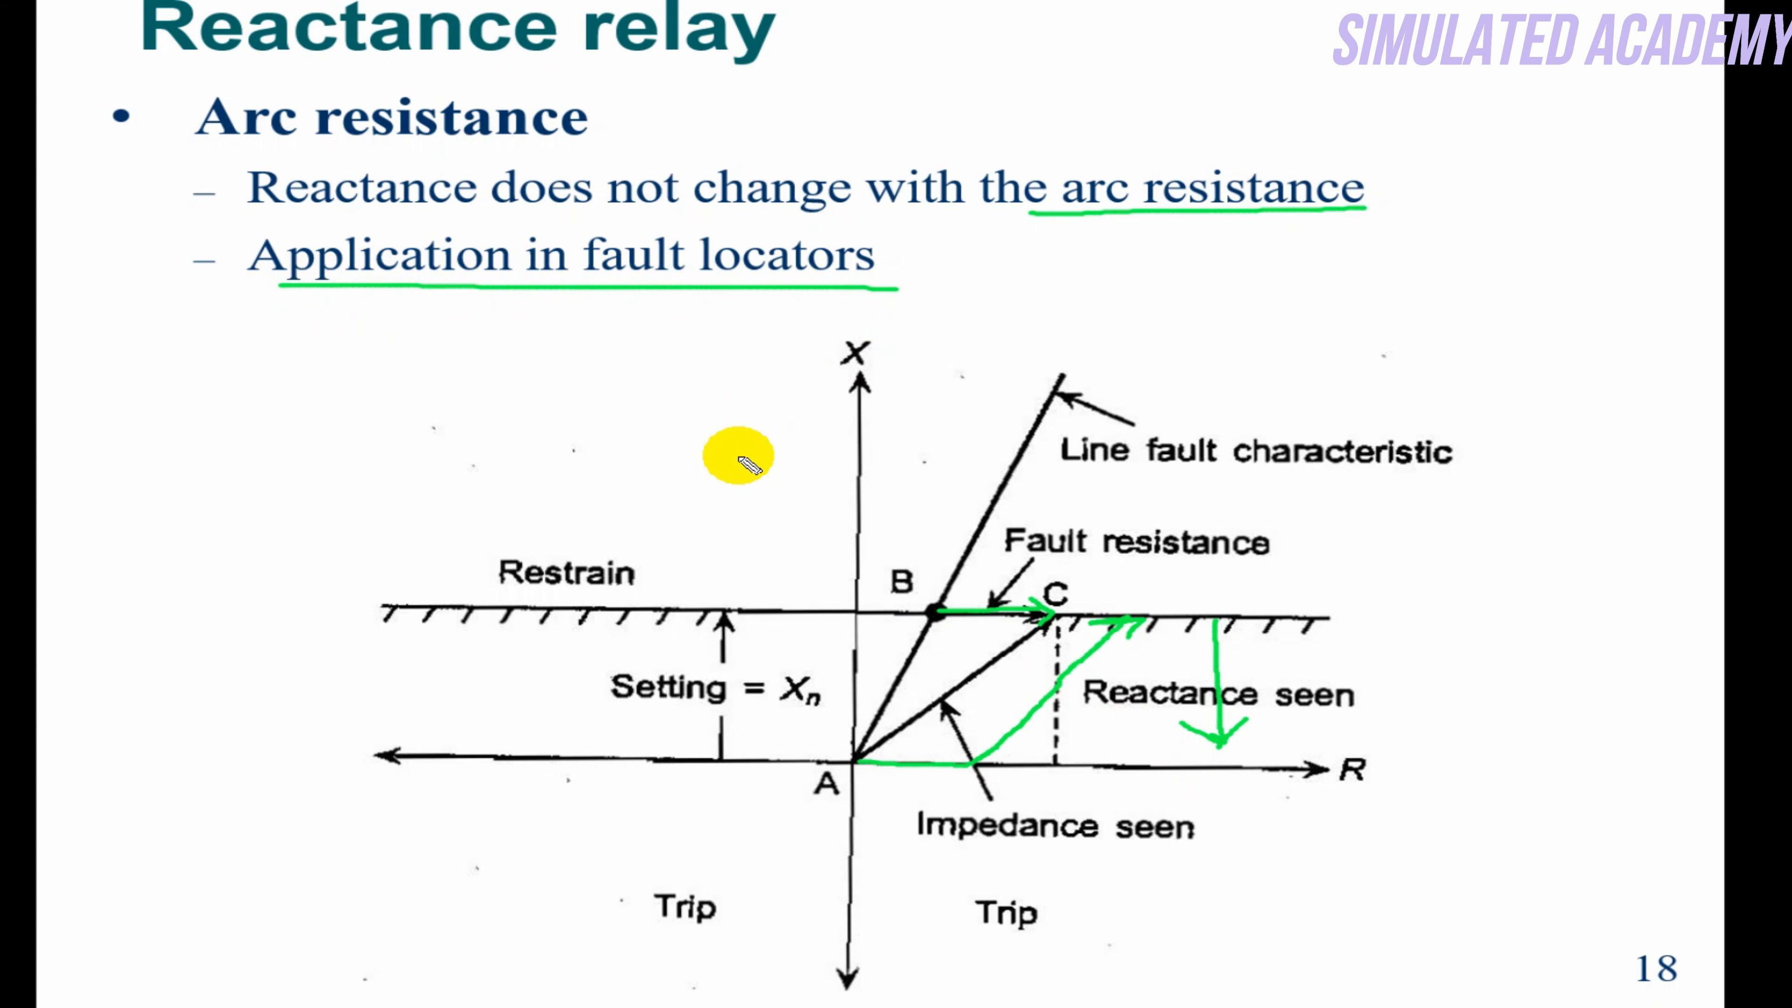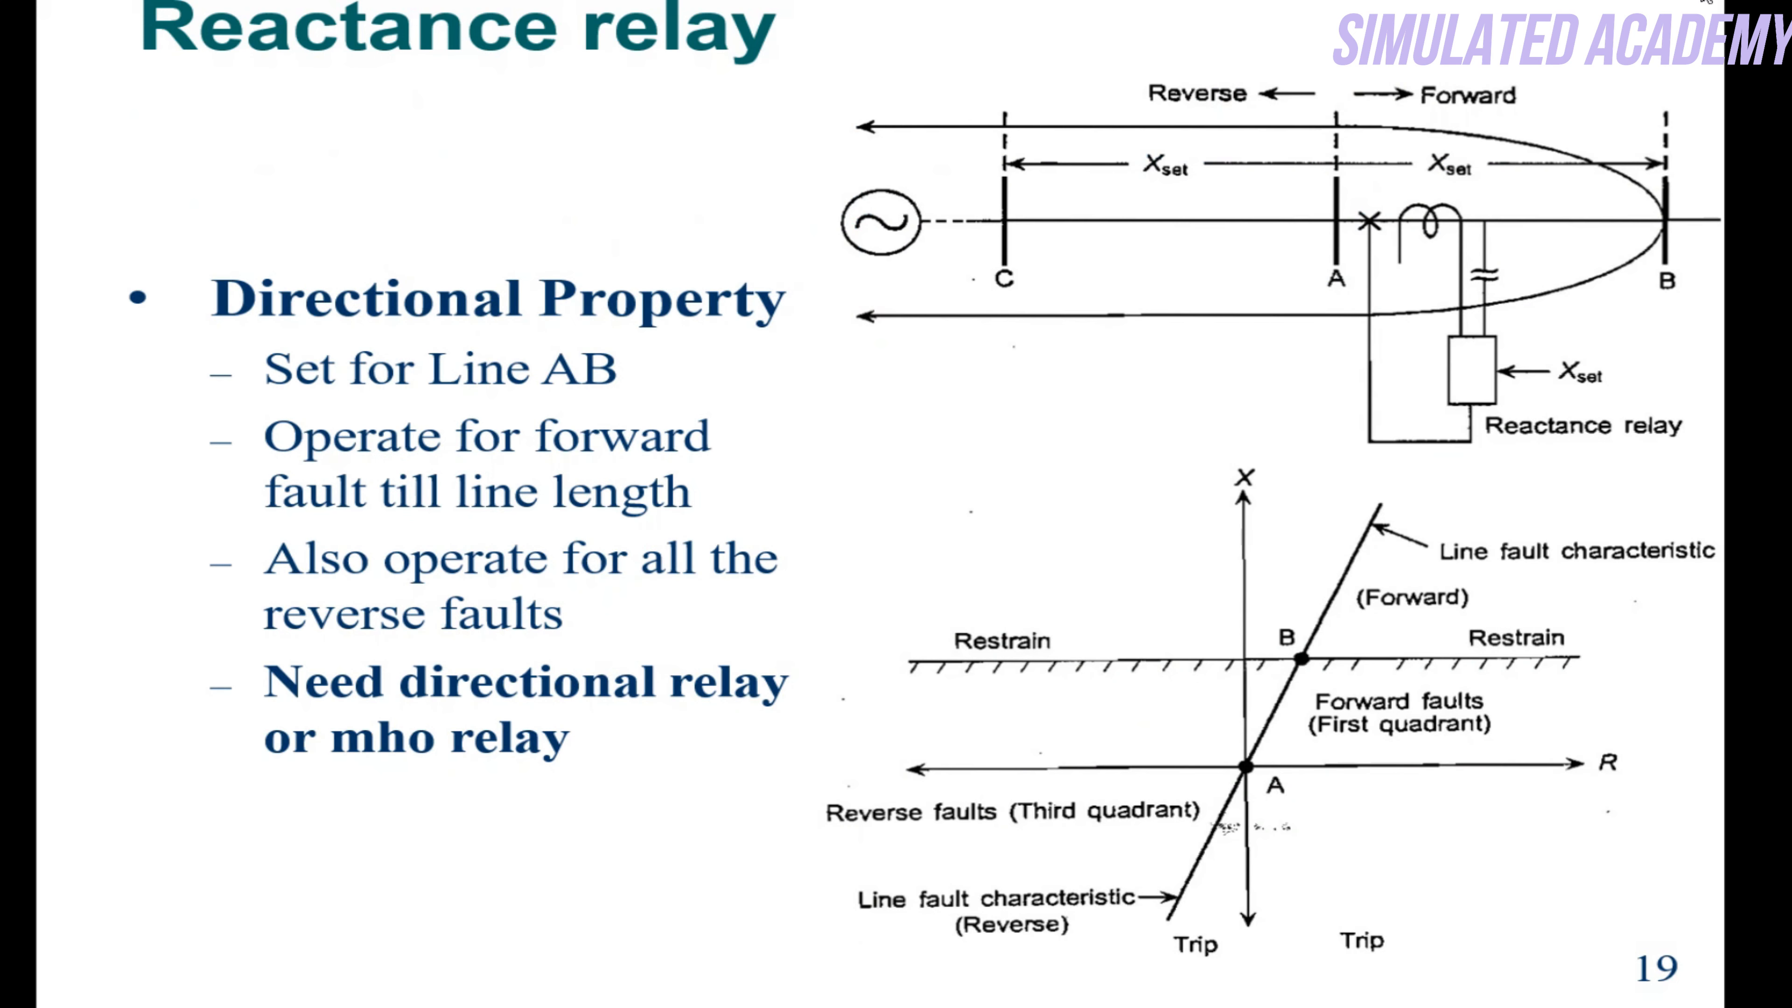If cables are used, you can use this for fault location. There is no directionality in this. If a fault is in any direction—for example, this is forward current, this is reverse current—it will operate for reverse current and also for forward current. So this means there is no directionality. For directionality, some other relay must be used—the mho relay, which we will discuss after this.